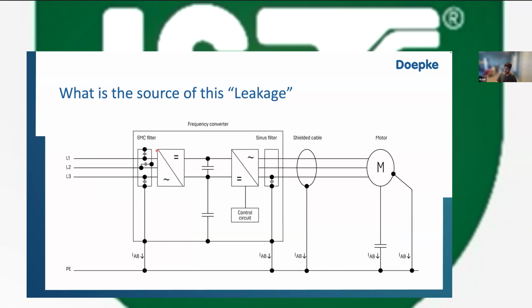Now, you may ask me, what is the source of this leakage? The first thing is that leakage current doesn't occur in the event of a fault. In fact, leakage current is defined as current flowing in the absence of a fault. But to an RCD that is sitting over here, it may look like we have a fault. And why is this? You have a filtering capacitor in the circuit here, here, and here, and this is required for EMC. To this filtering capacitor, you have current flowing like this, also like this, and like this. And for the RCD, it looks like some amount of current flowing through here is bypassing the RCD. So it appears like a fault.